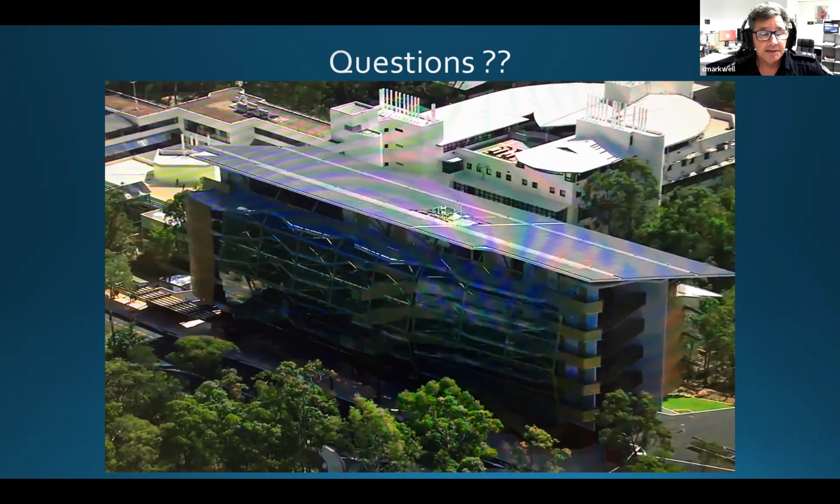And that comes back to the hazmat notification signage on the door, on approach. Again, arguably you need to know your own backyard, but we didn't even know this installation was in the building. So there's a lot of questions about regional area knowledge and information sharing between agencies. But again, there was no prescriptive requirement for hazardous placarding on this particular room. So all they had was a little sign that said electrical hazard, do not enter. Yes, not much of a sign, is it?